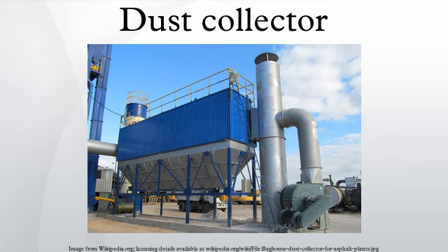The degree of dust collection required depends on its potential as a health hazard or public nuisance, the plant location, the allowable emission rate, the nature of the dust, its salvage value, and so forth. The selection of a collector should be based on the efficiency required and should consider the need for high-efficiency, high-cost equipment, such as electrostatic precipitators; high-efficiency, moderate-cost equipment, such as baghouses or wet scrubbers; or lower-cost, primary units, such as dry centrifugal collectors.